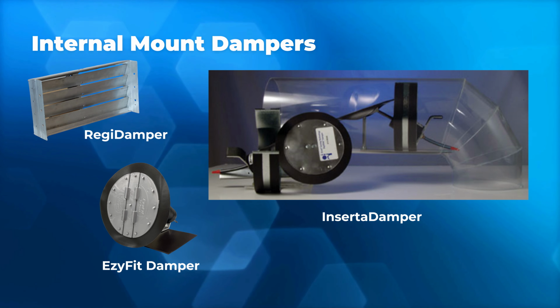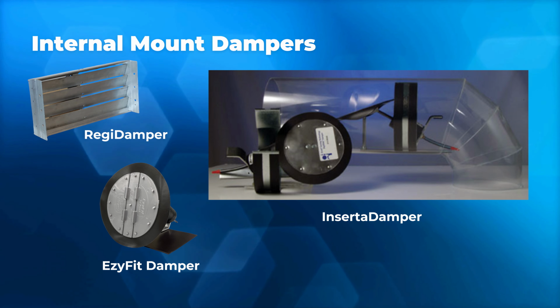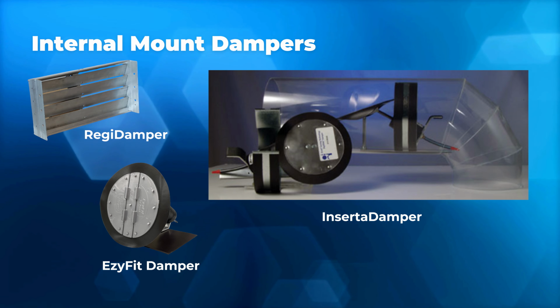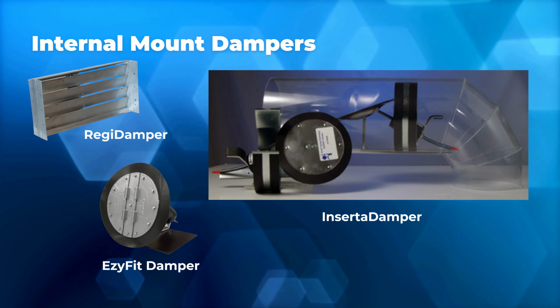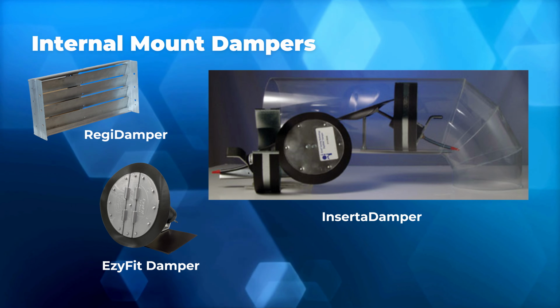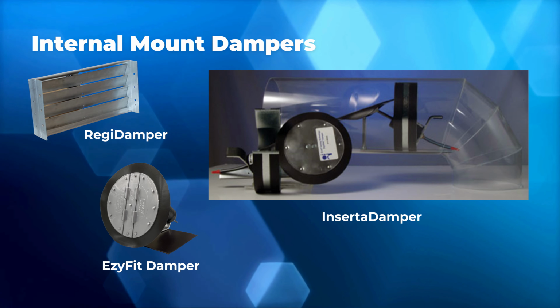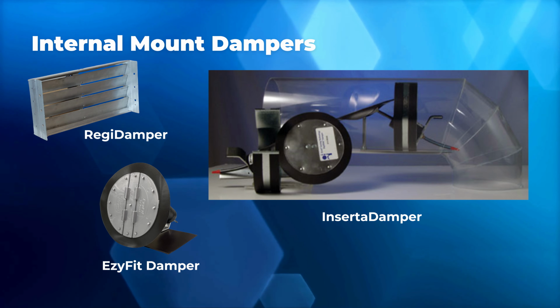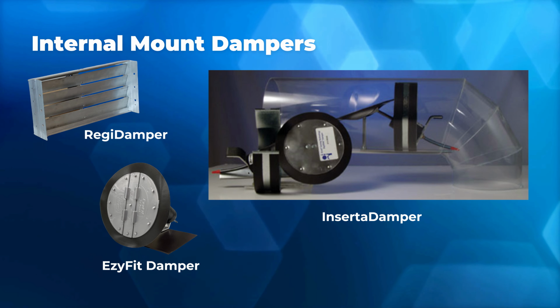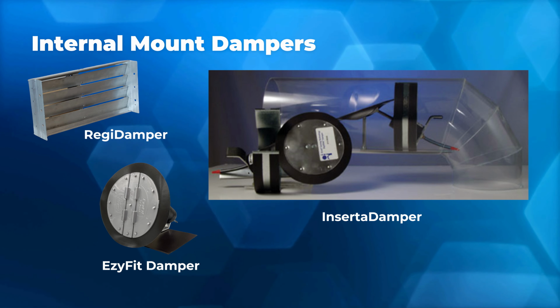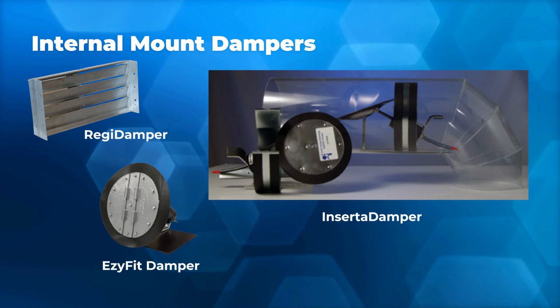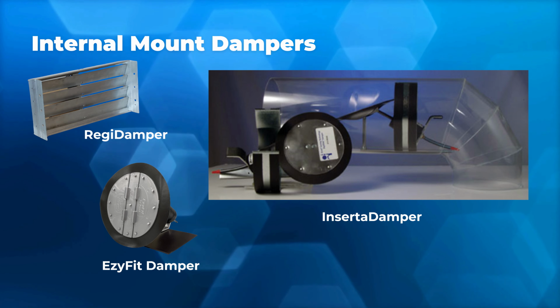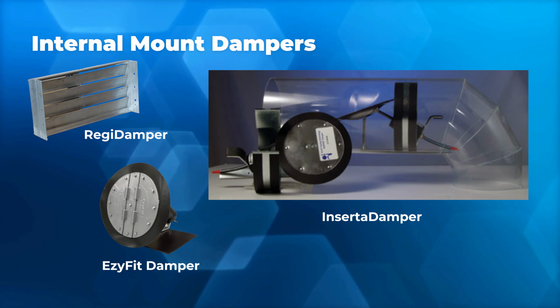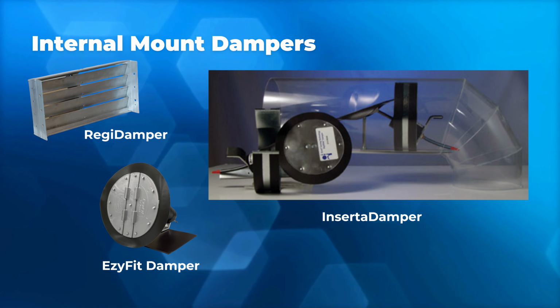And then the next damper in the middle there is going to be our EzyFit damper. What this one does, if you guys can see in the middle of that blade there, the blade folds up in half, and then it's got a magnet that holds it in place. So essentially you can fold this whole damper in half, kind of like a taco, and you can actually reach right through your register grill, right down into the boot itself, and insert this into your supply run. The magnet holds it in place so it's not going anywhere, and then you just run your tubing back.